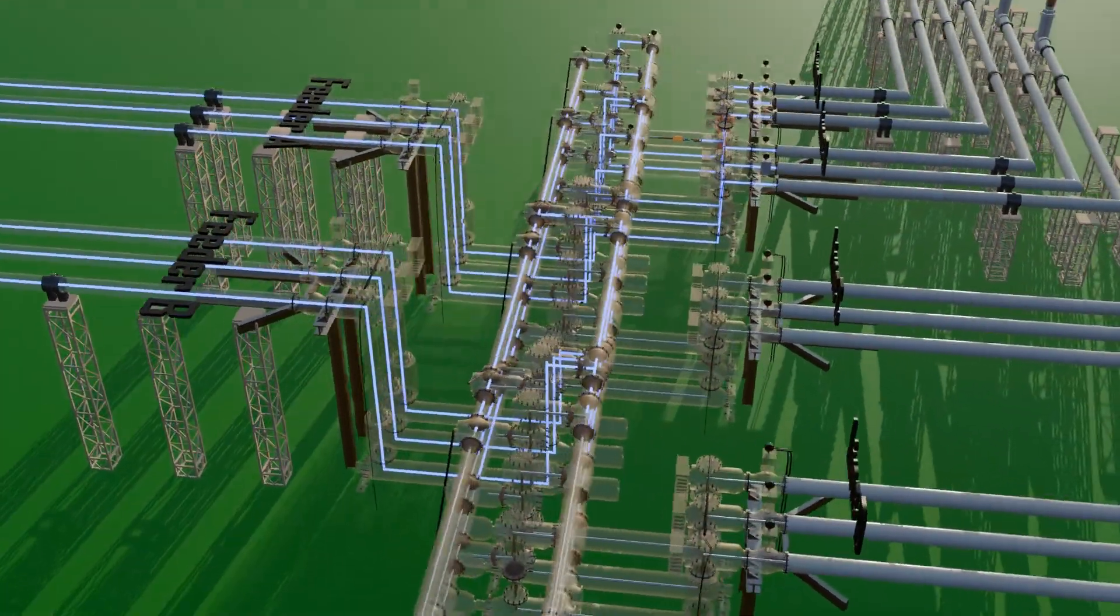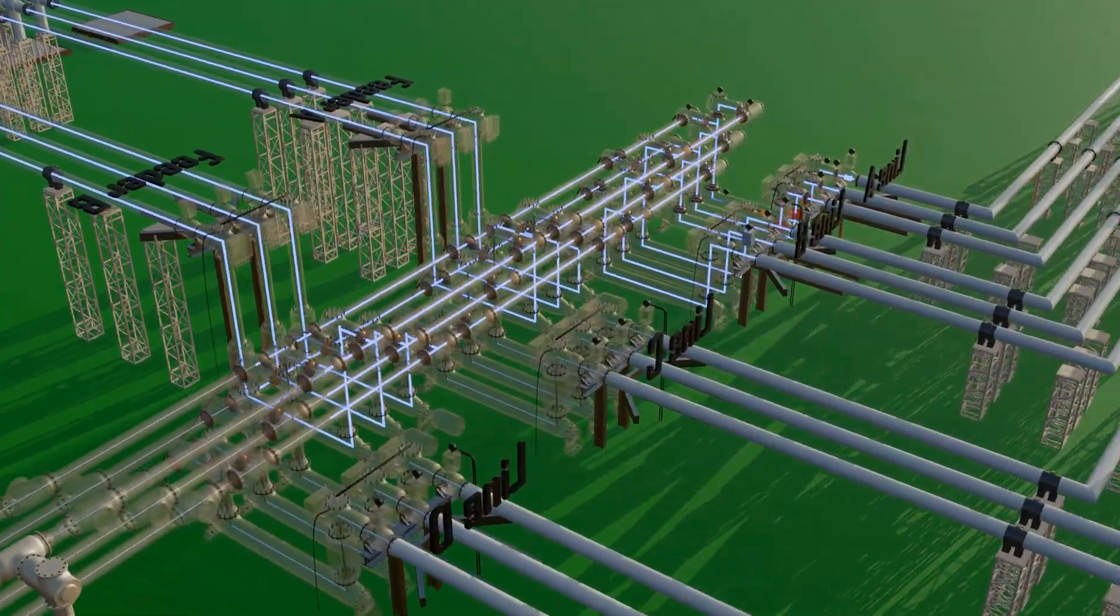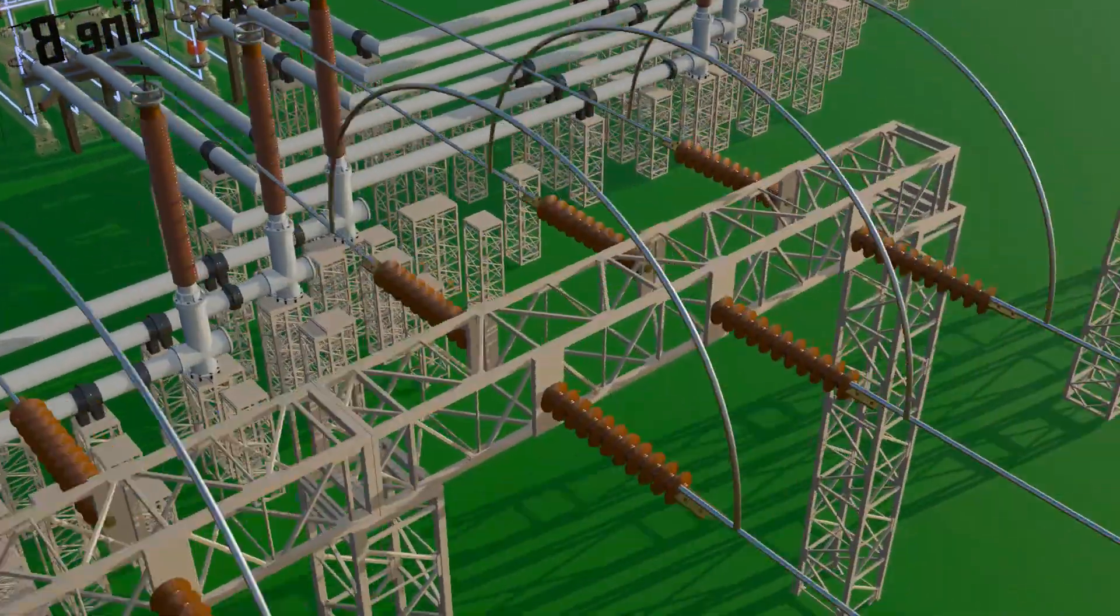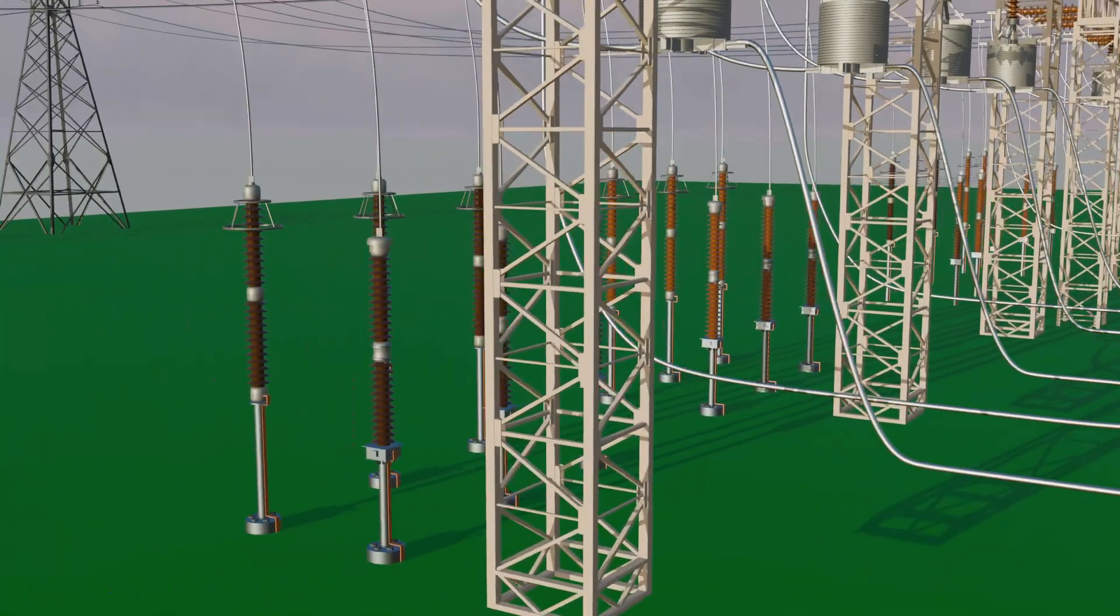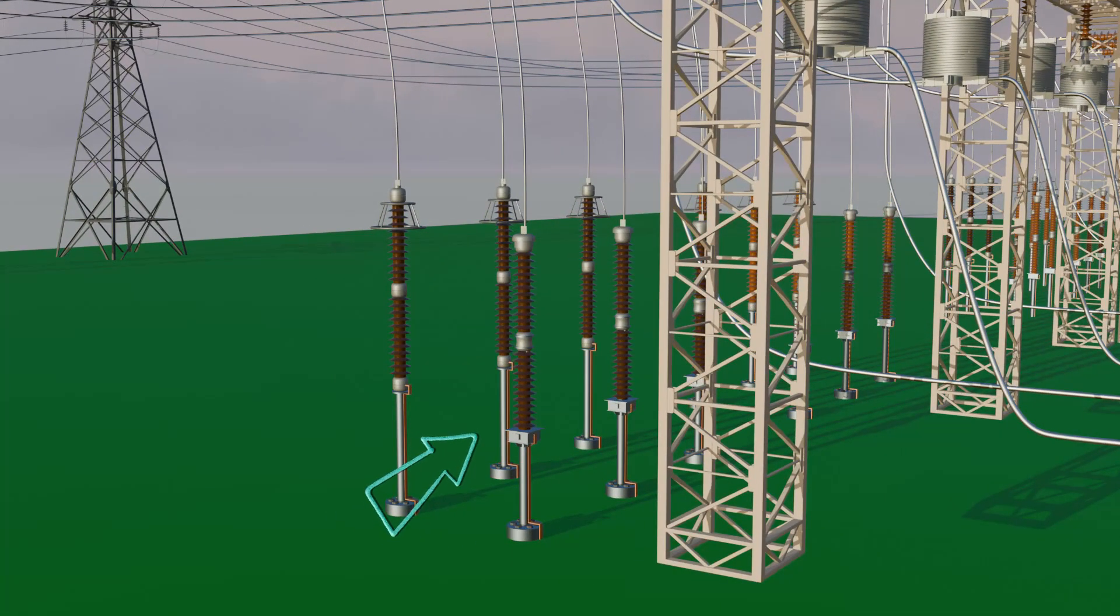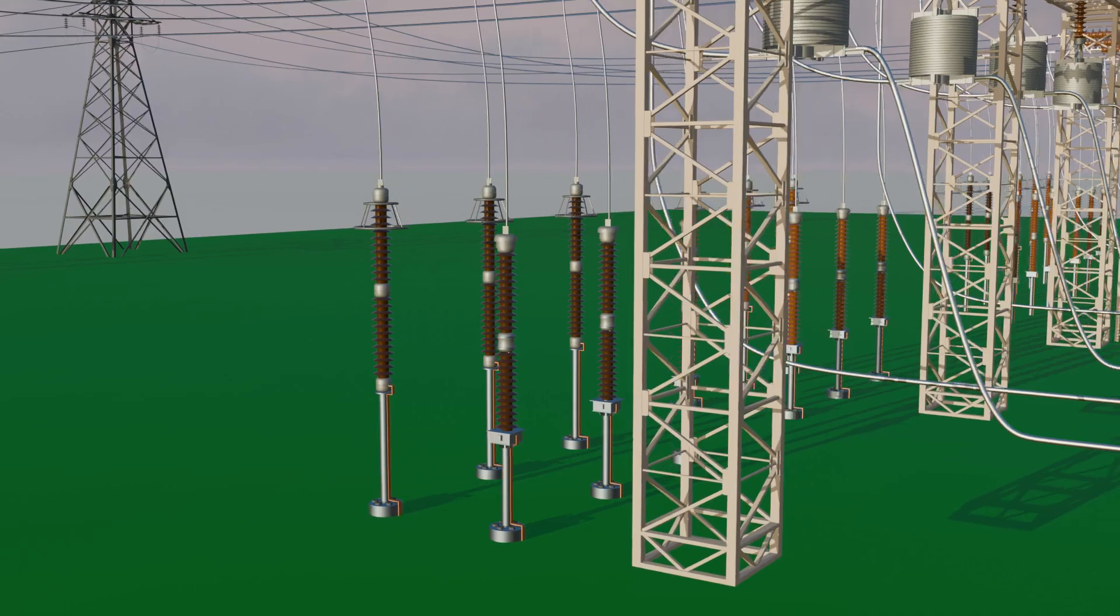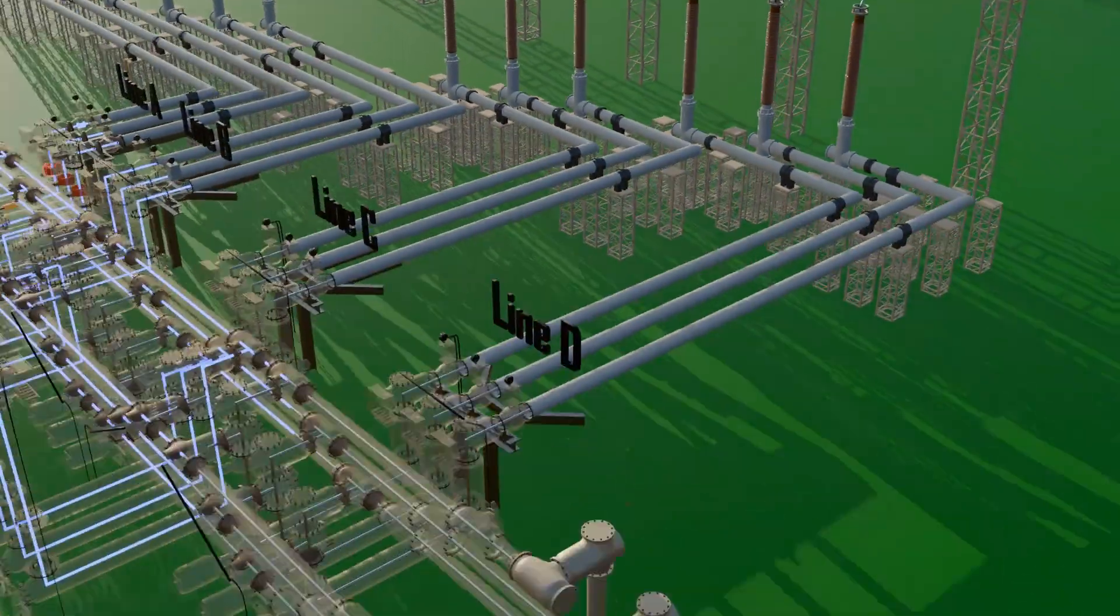One important point: we saw that after the lightning arrestor, a CVT is used to measure voltage. But suppose there is not enough space to install the CVT outside. In that case, a CVT can be installed at the far end of main bus 1 or main bus 2 inside the GIS to measure bus voltage.